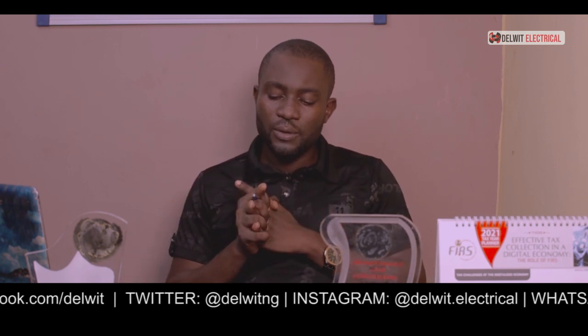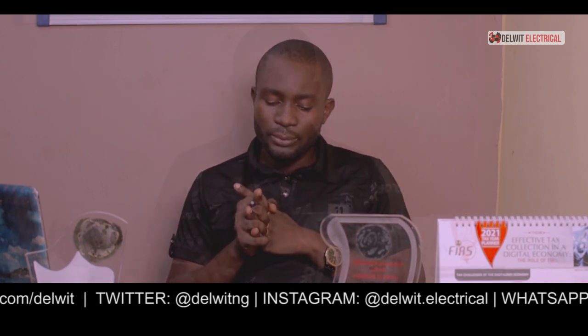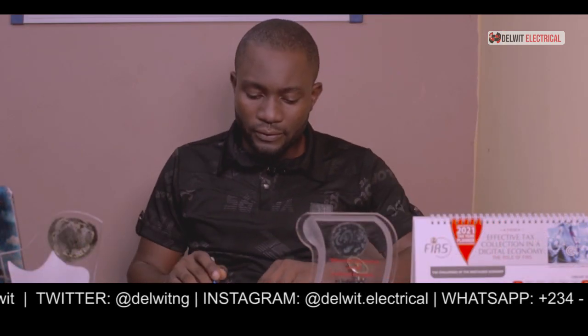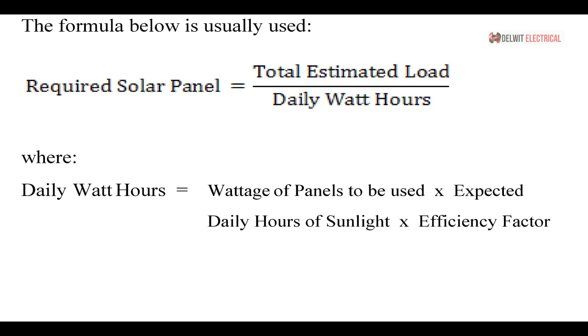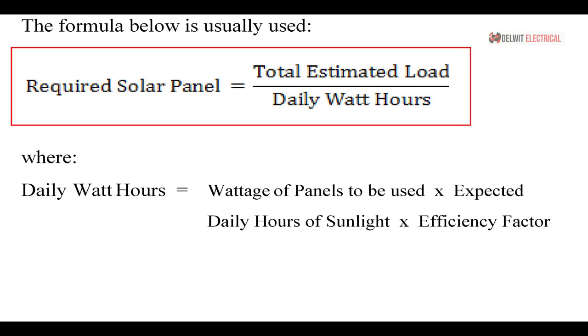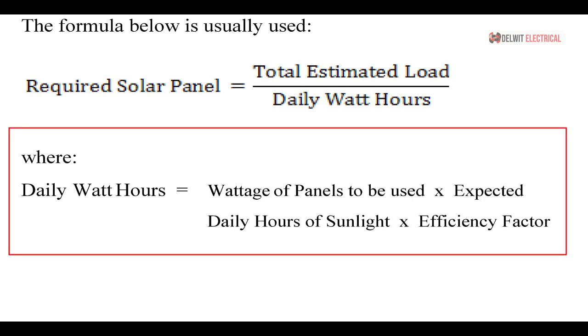We need to carry out a calculation to determine the number of solar panels required for your building. There is a standard formula: Required Solar Panels = Approximate Total Load ÷ Daily Watt Hours. The Daily Watt Hours formula is: Wattage of Panels × Expected Daily Hours of Sunlight × Efficiency Factor.